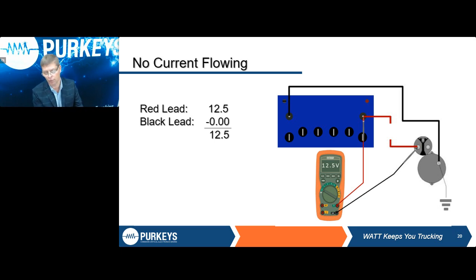And we could use that voltmeter and walk all the way through that circuit from point A to point B, from point B to C, C to D, walked all the way through it to look at the voltage drop of every single part of that circuit. That way you can go back through and say, yes, I have a voltage drop. And by isolating it down, I can tell you it was a voltage drop between the fuse panel and the bulkhead connector going through the firewall. So a voltmeter can flat talk to you using it this way and walking through the circuit.